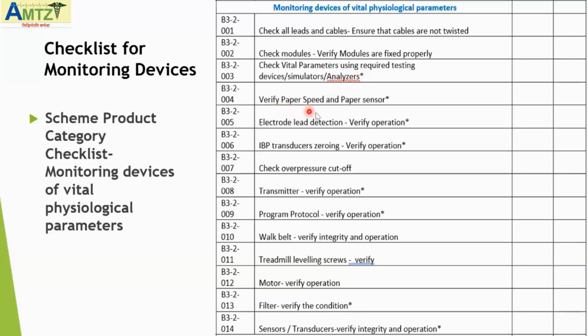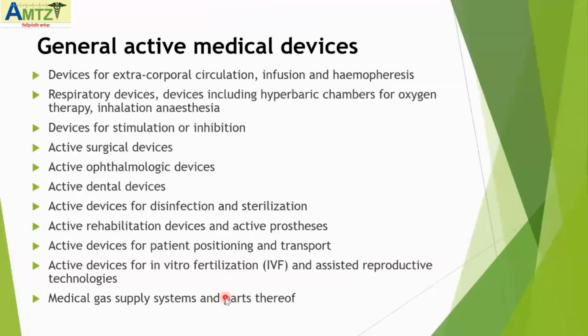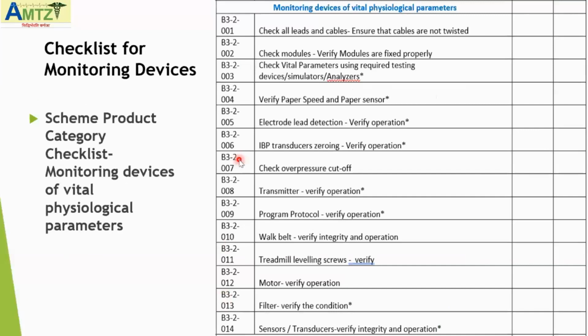Then you verify the paper speed and that the paper sensor is working. Some ECG machines have a paper sensor, so you check whether it is working or not. These are some of the checklists that we have formulated. Again, I repeat, it is a minimum, and you can always put in more things. But when you put in more, it becomes extra, so that your device is maintained in a good manner, more stable. For this scheme product category, there are 14 points in total.